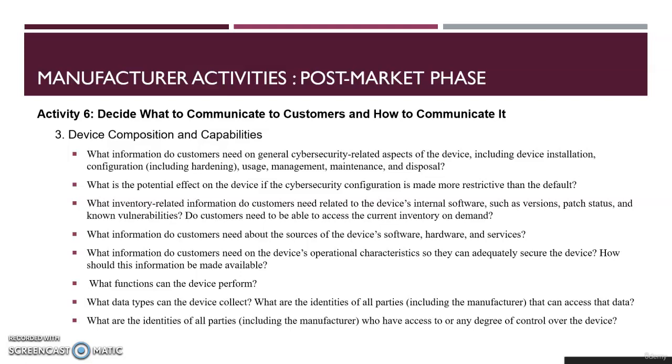What functions can the device perform? This includes not only the device's cybersecurity capabilities but also any other function that may have cybersecurity implications, like transmitting data to a remote system or using a microphone or a camera to capture audio and video. What data types can the device collect? What are identifiers for all the parties? What are the identities of all parties who have access to or any degree of control over the device?